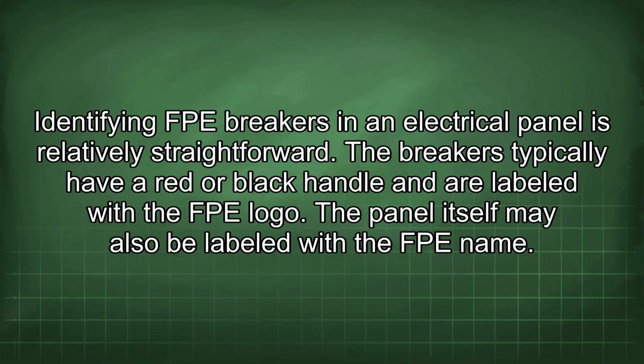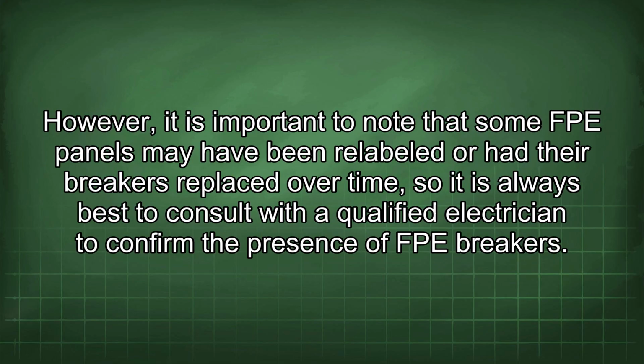Identifying FPE breakers in an electrical panel is relatively straightforward. The breakers typically have a red or black handle and are labeled with the FPE logo. The panel itself may also be labeled with the FPE name. However, it is important to note that some FPE panels may have been relabeled or had their breakers replaced over time, so it is always best to consult with a qualified electrician to confirm the presence of FPE breakers.